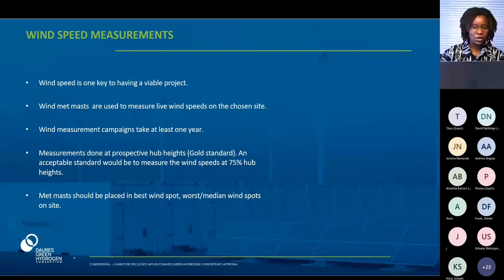An acceptable standard would be to measure the wind speed at 75% of hub height. So if your wind turbine is at a 120 meter hub height, your met mast would be at, say, 90 meters. The met mast should be placed in the best, worst, or median wind spots on site.